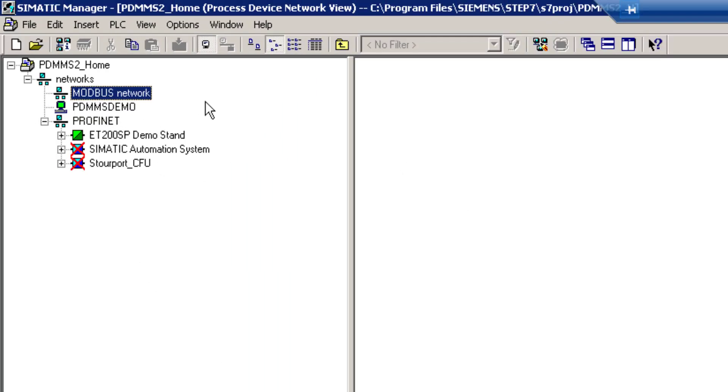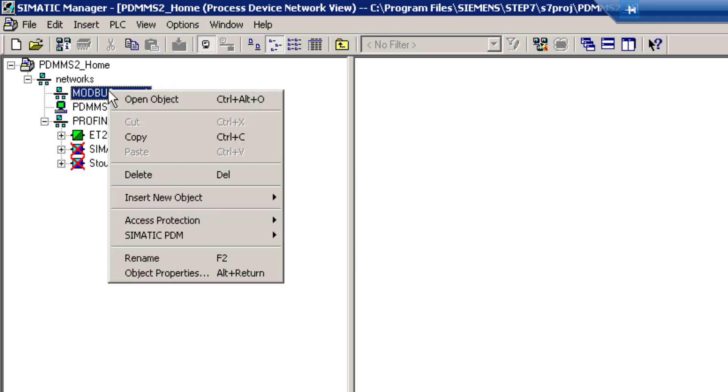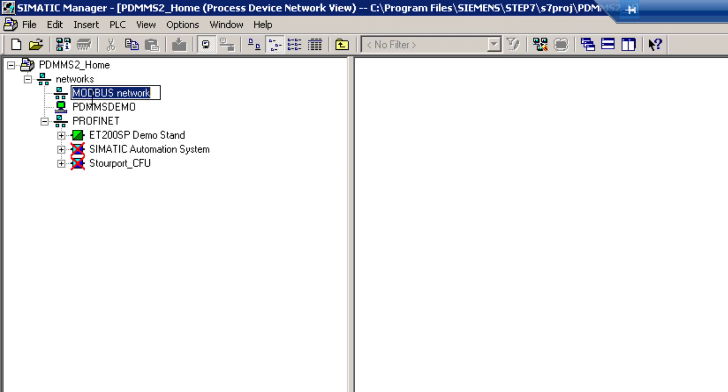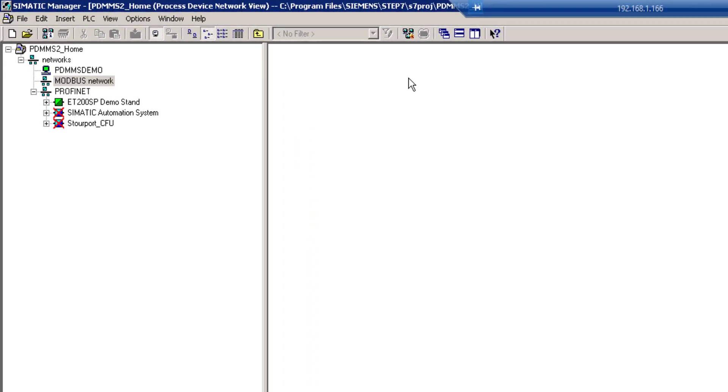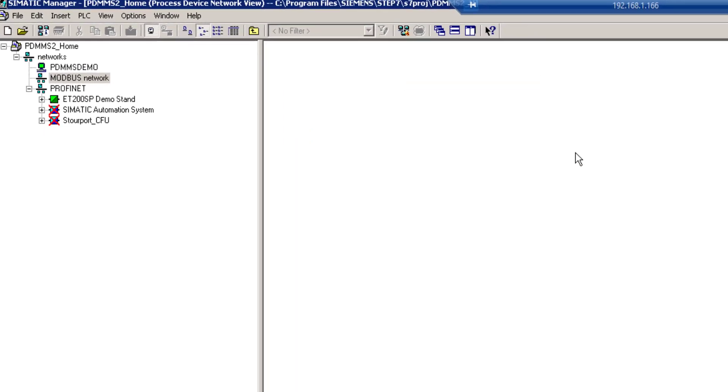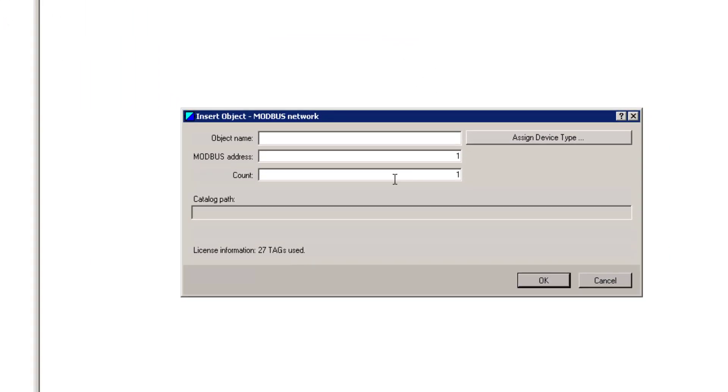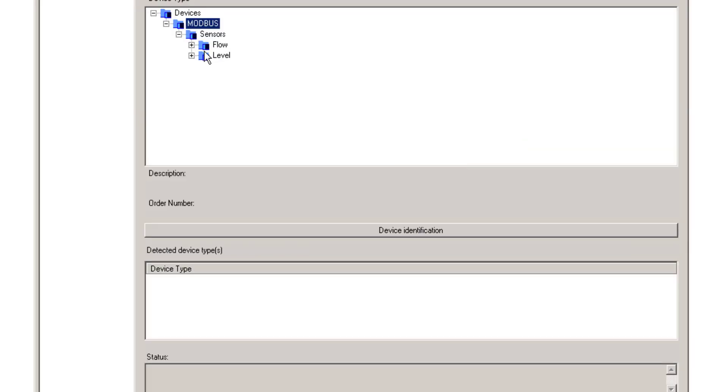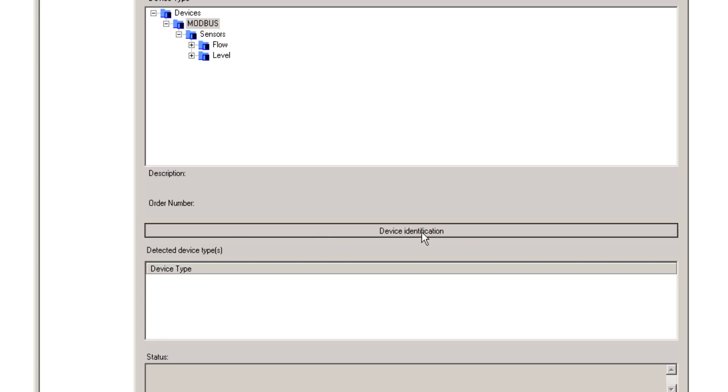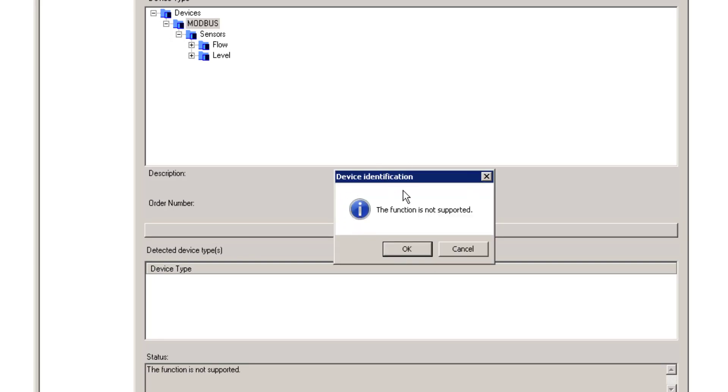Now we've added the network. All that remains is to add the device itself. With the MODBUS network selected, on the right hand side insert a new object. Here you have the MODBUS address. The default MODBUS address for the Sitrans FC410 is 1. I'm going to show you how to change that. So the first time you connect to a new device, you'll have to set it up as 1. We'll assign the device. You have to manually select because device identification is not supported for MODBUS connectivity.